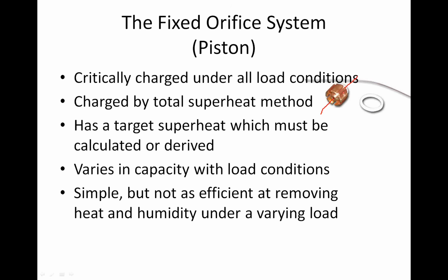But the normal way it works is this gets front seated and against this gasket, and all the refrigerant is forced to go through this little metering device. These are critically charged systems under all load conditions. Okay, when we were looking at that superheat chart and it said 15.8 degrees, it means 15.8 because it's 15.8. That's what it needs to be charged to. So you need to be within a degree or two of the target superheat. Otherwise, you're going to be undercharged or overcharged.